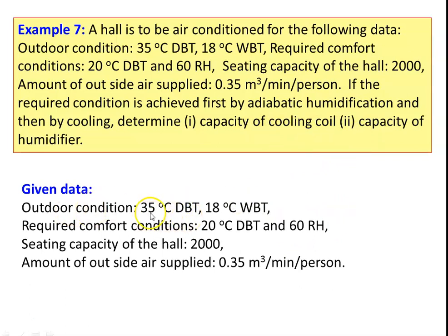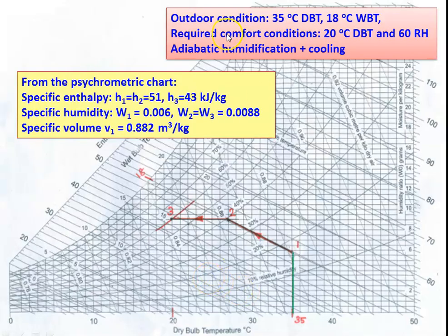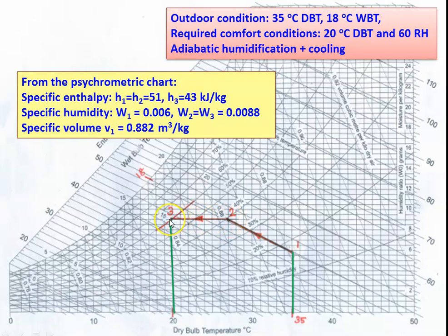Given data: outdoor conditions 35 degree Celsius dry bulb temperature and 18 degree Celsius wet bulb temperature; required comfort conditions 20 degree Celsius dry bulb and 60 percent relative humidity; seating capacity 2000; air supply 0.35 cubic meter per minute per person. On the psychrometric chart, draw a constant enthalpy line from point 1 (outdoor) and a horizontal line from point 3 (indoor) — these meet at point 2. Process 1 to 2 is adiabatic humidification; process 2 to 3 is cooling.